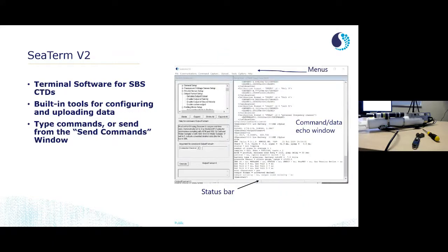Next we're going to talk about Seaterm V2. This is the software you use to talk to your 19 plus V2, terminal software made for Seabird Scientific CTDs. You can use a different terminal like PuTTY or TeraTerm to talk to your 19 plus V2, and that'll work fine. However, Seaterm V2 has tools built in for configuring your instrument and uploading data from it. You can type commands into the window, or send them automatically from the send commands window on the left. I'll demonstrate that momentarily if you don't know the commands for your 19 plus V2.